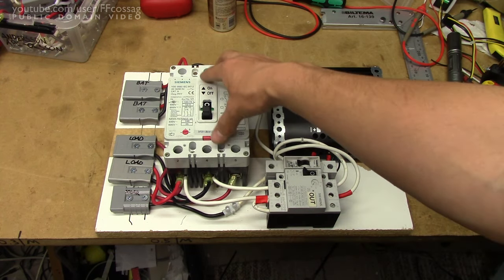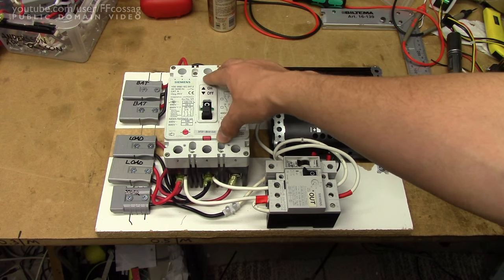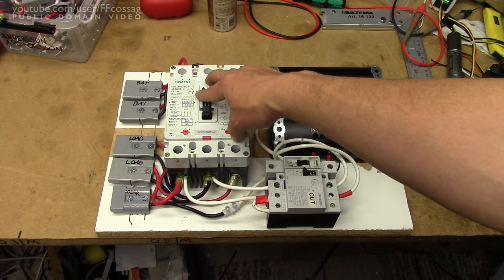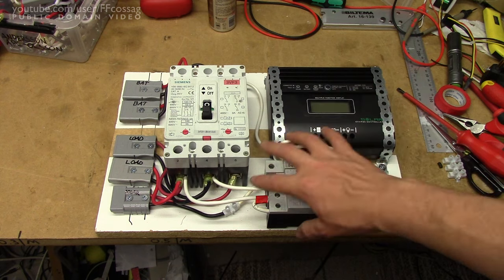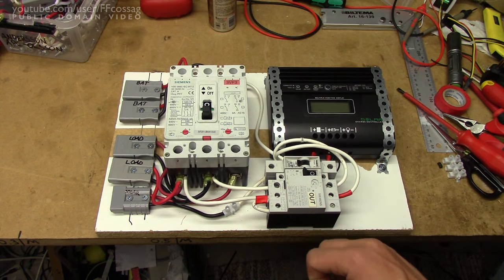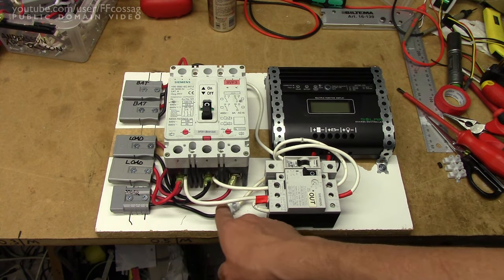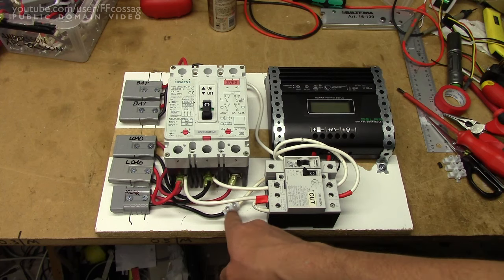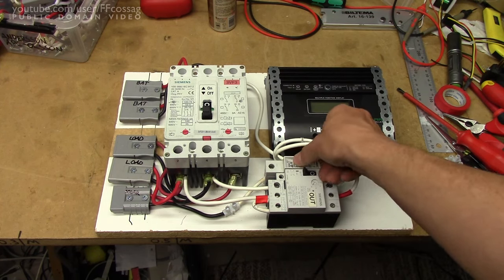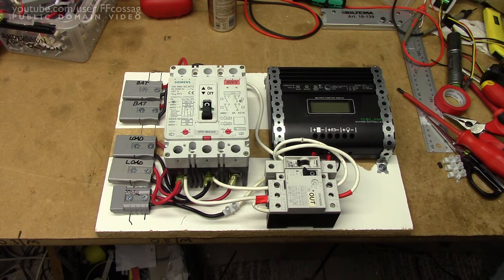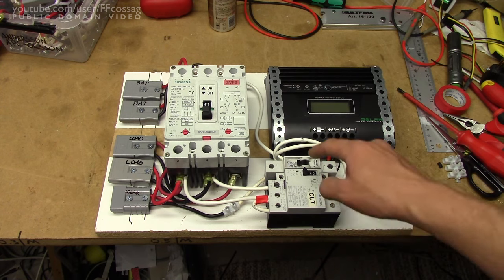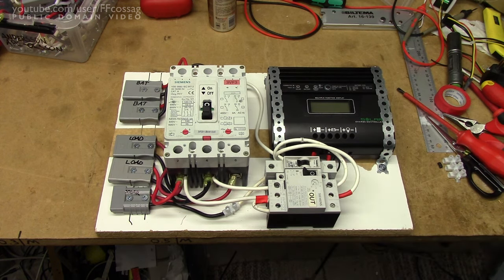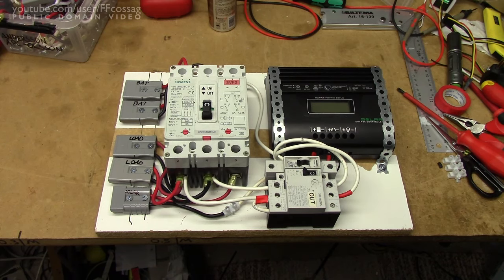In case there's an overload condition on this so that this would flip, but not the solar panel, so that we wouldn't have all kinds of weirdness going on on the actual load side. The other end of the solar connector just goes straight to this little tiny extension and into the solar breaker where I can turn off the solar panel individually if necessary. A little 10 amp breaker. So that's the connection, let's give it a test run.